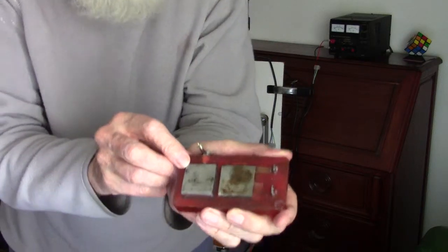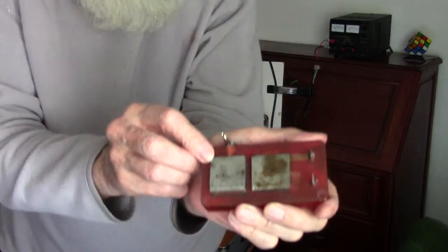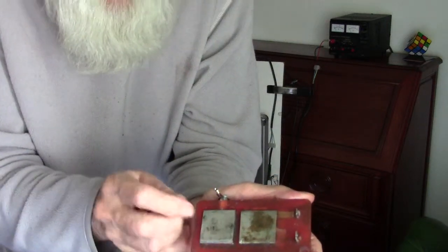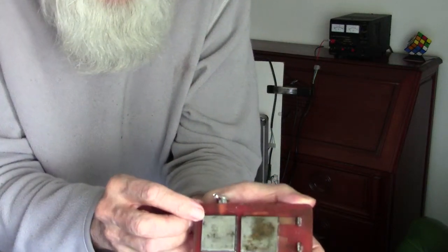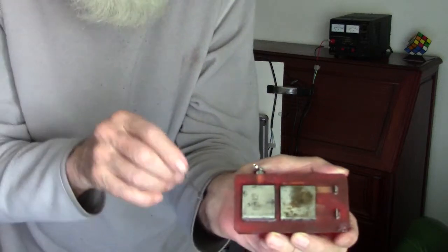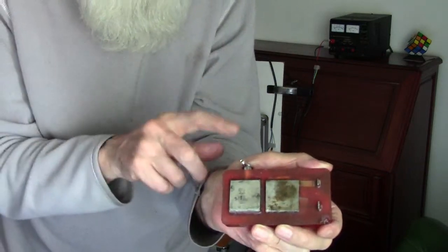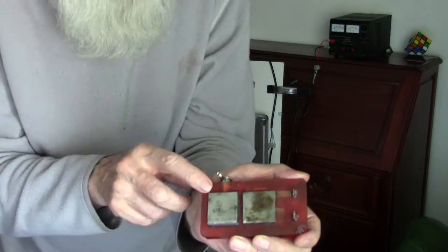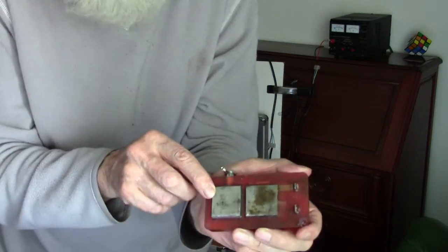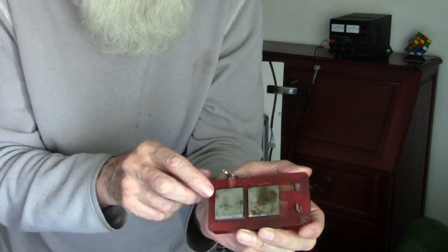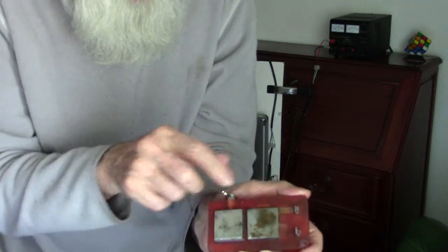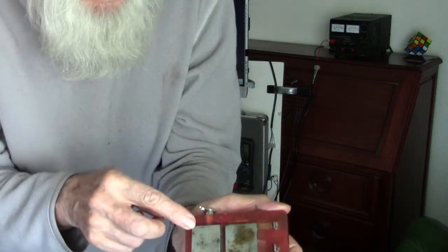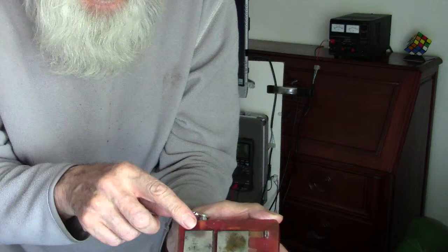This is polished before each time of use, and you can see the very small amount of corrosion that's happened during this very short time that we have been actually undergoing the test. Don't forget, a lot of the time of the test this has been protected. So there'd not only be corrosion current flowing from here, but there'd be cathodic current flowing onto this from the cathodic protection system.